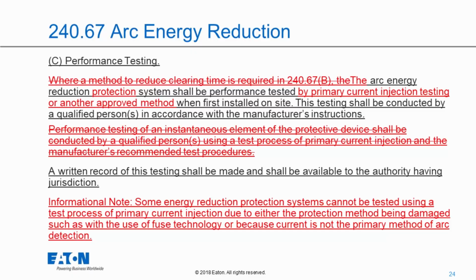Or because it is not the primary method of arc detection. So, for instance, maybe you have an arc flash relay. You have the current aspect, but you also have the light aspect. So, you know, maybe you would not want to primary current injection test that type of technology either.